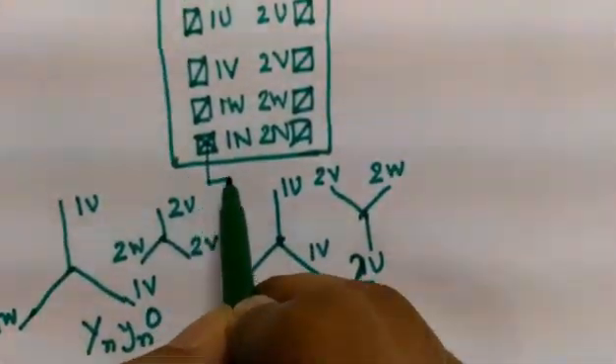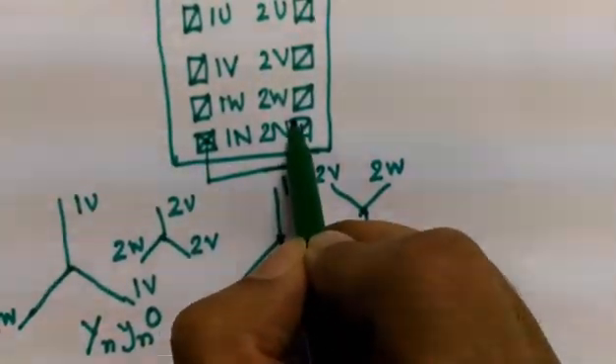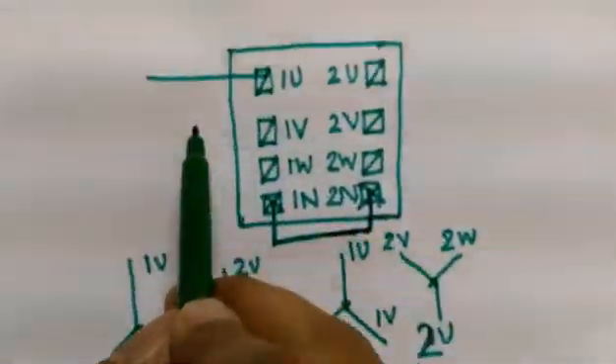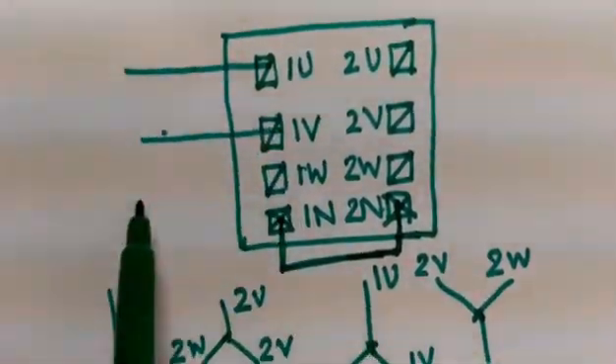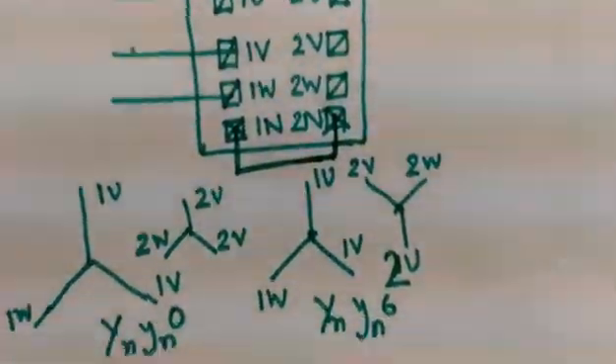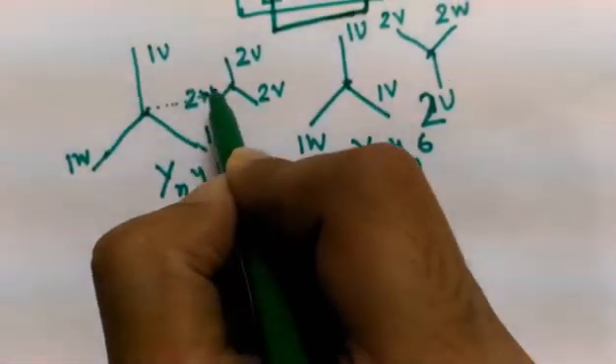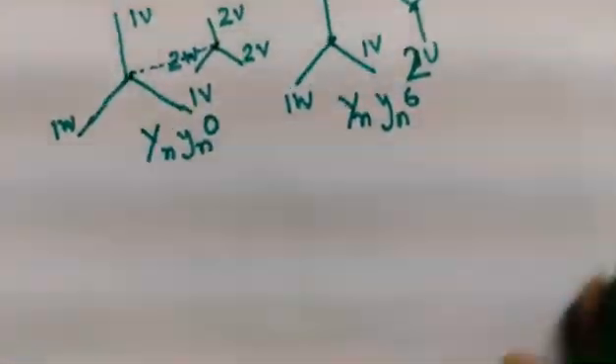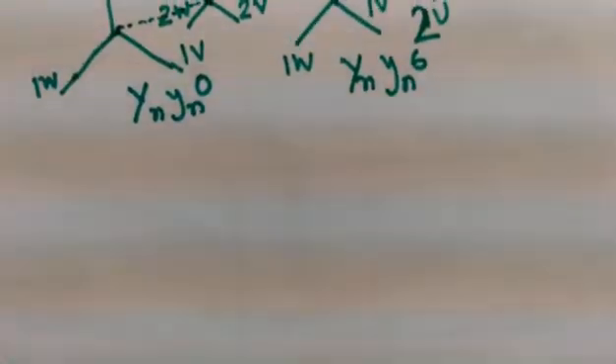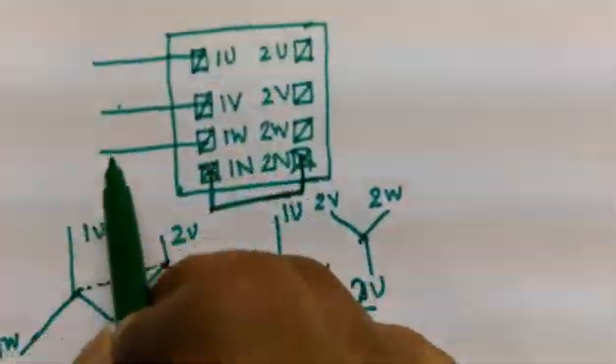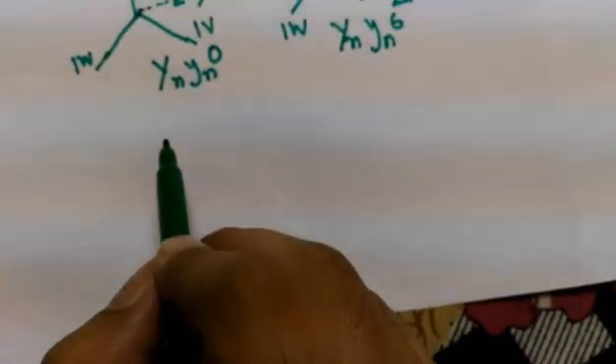For detecting the vector group, what we have to do is first short the two neutral points — we have shortened the two neutral points. Then we will apply a reduced voltage to the high voltage winding, and the secondary will have the induced voltage as per the turns ratio. What we have basically done is connected these two neutral points together.